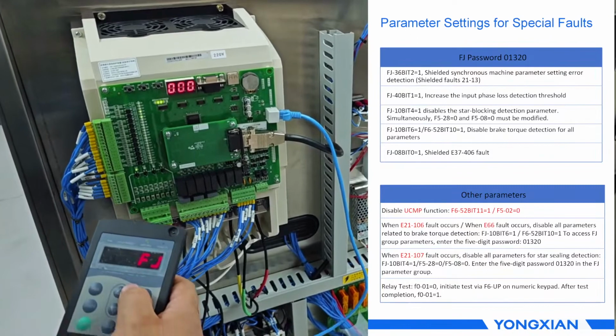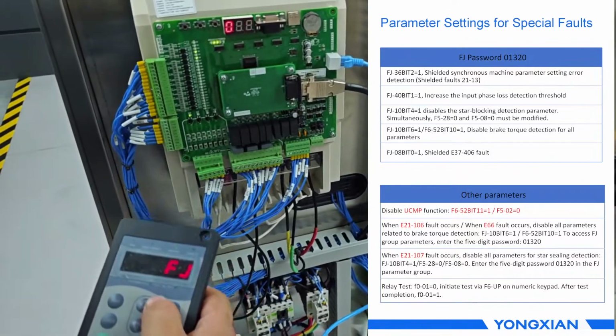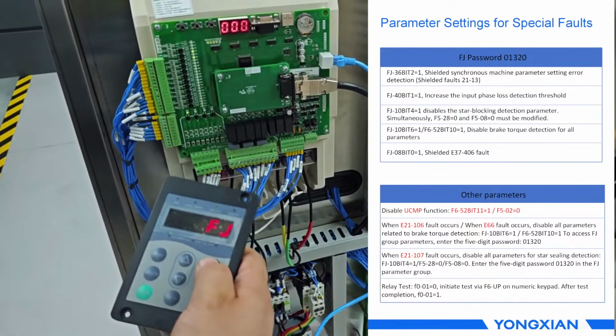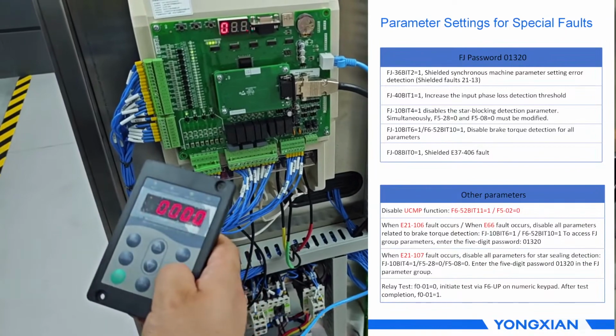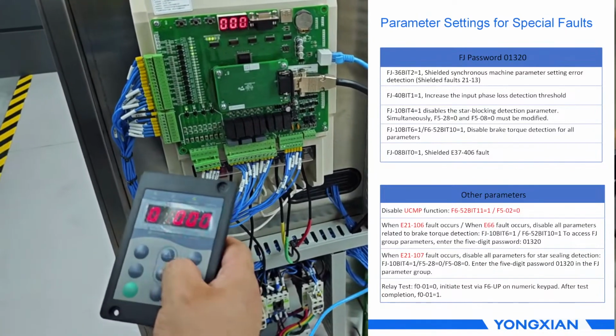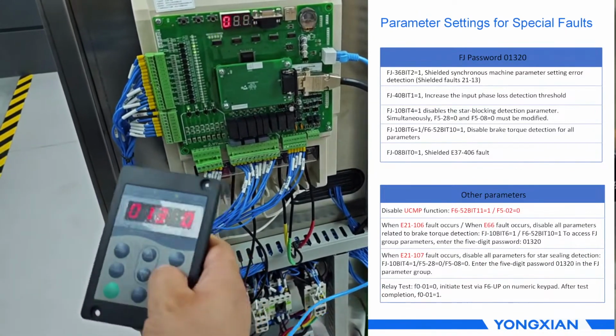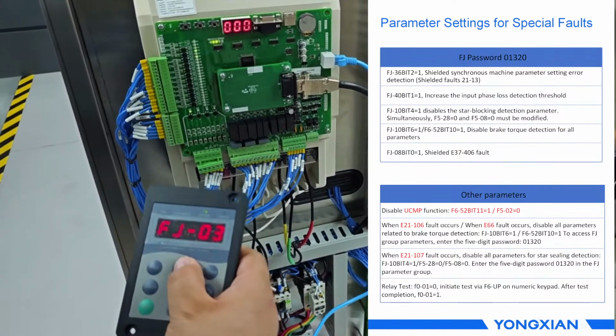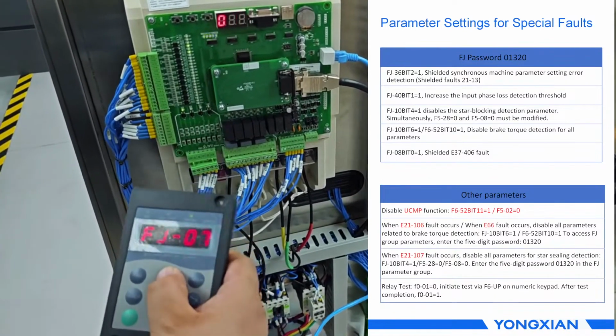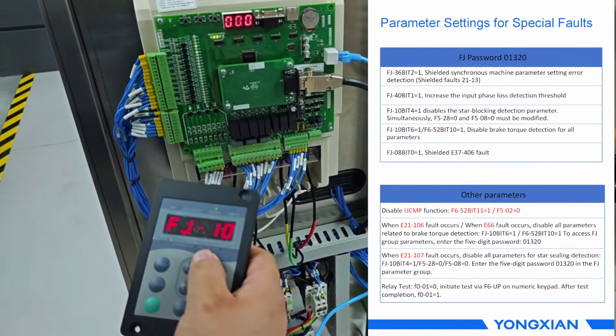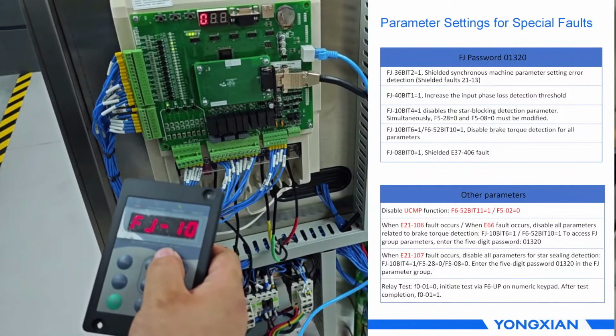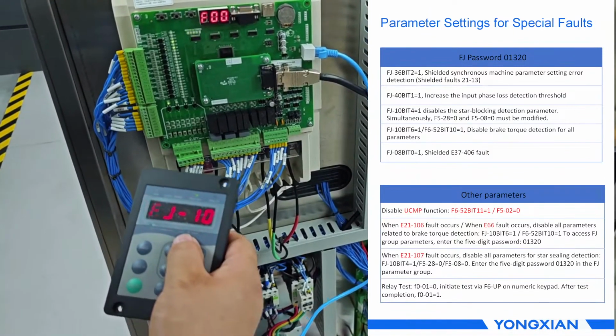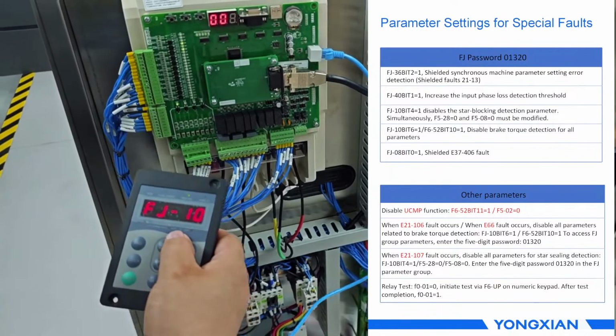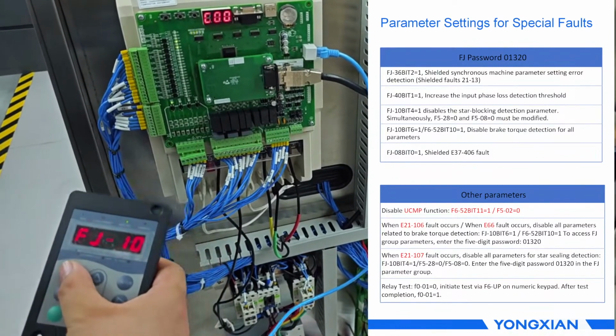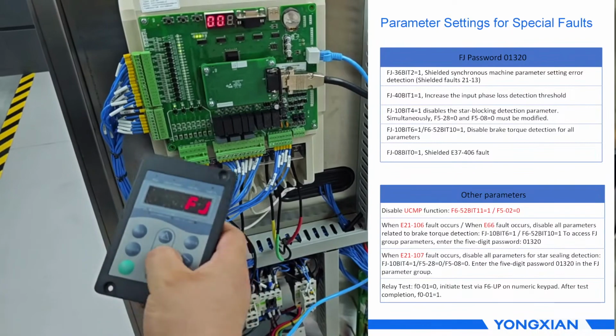然后21-107故障。To access FJ group parameter, enter the 5-digit password 01320. And when E21107 fault occurs, FJ-10 bit 4设为1。Set the FJ10 bit 4 equals 1.